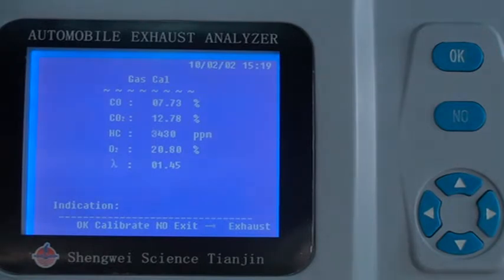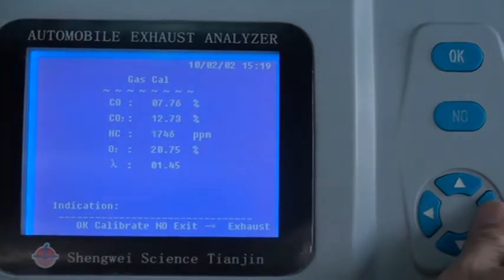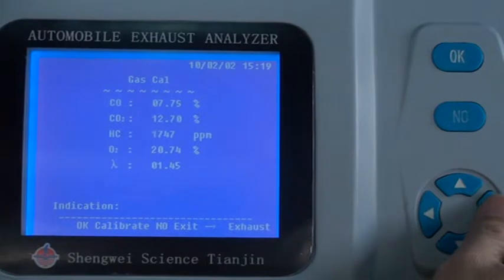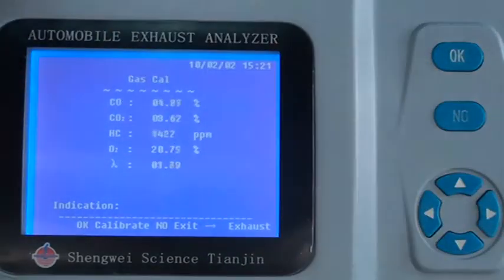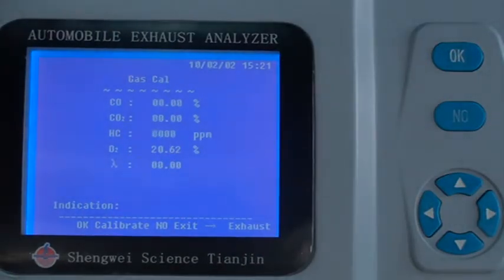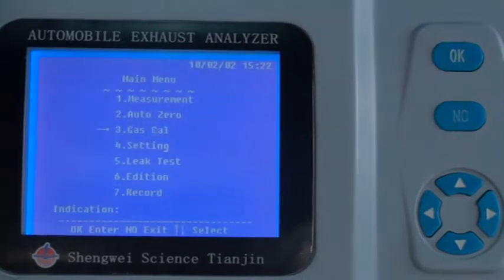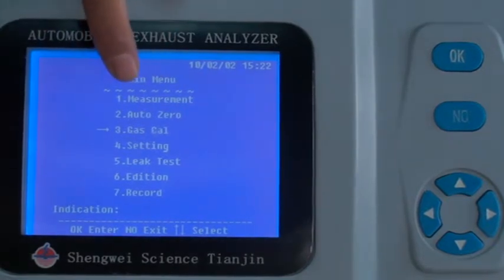You don't need to exit. Press OK, and when you hear the ring sound, the buzzer, the calibration operation is finished. Then press the right key to vent the gas. When all the numbers show 0, press No to exit. Then it enters the measurement.